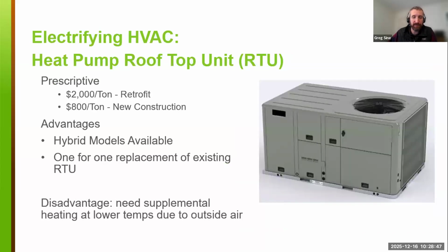We'll go to the next slide. Kevin had mentioned RTUs. There's a number of RTUs on the market now that incorporate heat pump technology, similar to air source heat pumps, the split type units we were just looking at. There's prescriptive rebates of $2,000 a ton for retrofit projects, or $800 a ton for new construction. Larger projects, or projects that serve variable air volume systems, we'd want to look at on a custom basis. But for your typical like-for-like replacement of a single zone RTU, usually that's a project we could handle with a prescriptive application.